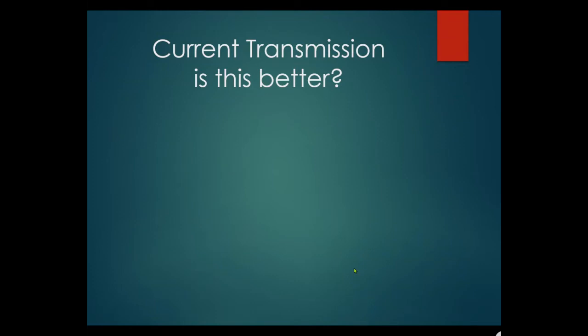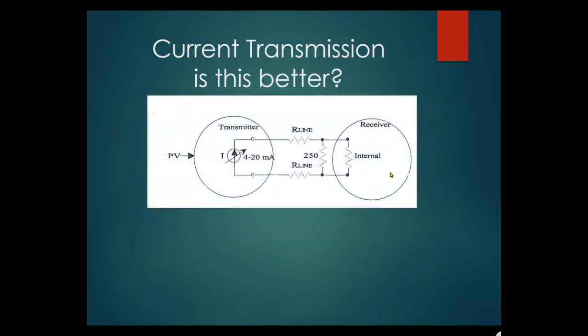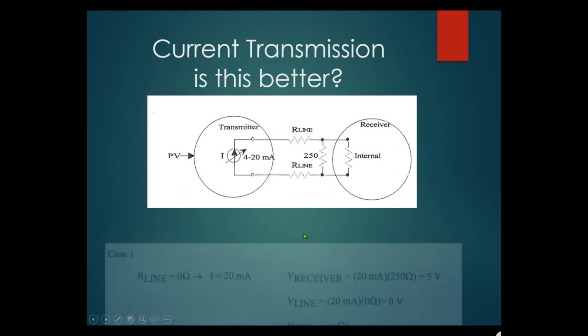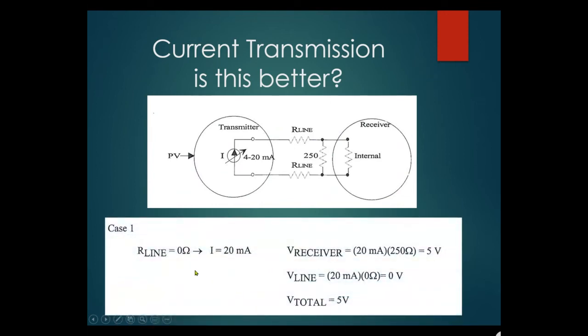Now let's talk about 4 to 20 milliamp current transmission. In the current loop diagram, there's a 250 ohm resistor and the voltage across it is 1 to 5 volts. Case one: R-line is zero ohms, current is 20mA. Voltage across receiver: 20mA × 250Ω = 5 volts. Voltage across line: 20mA × 0 = 0 volts. Total is 5 volts — exactly what we want.